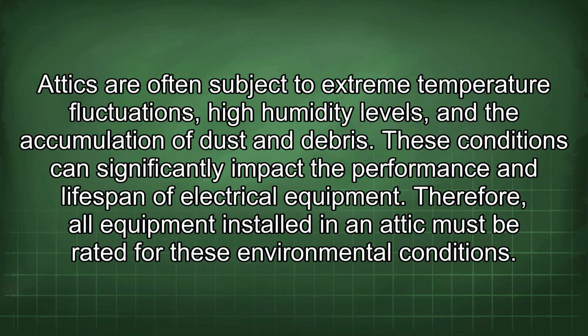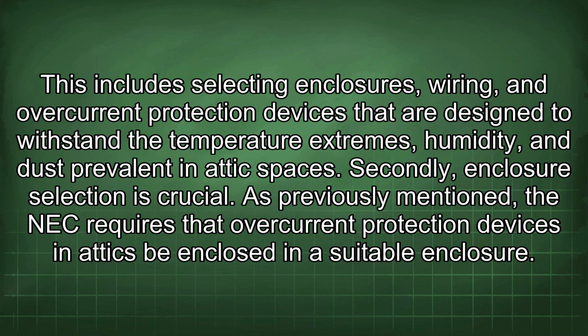Firstly, environmental factors are paramount. Attics are often subject to extreme temperature fluctuations, high humidity levels, and the accumulation of dust and debris. These conditions can significantly impact the performance and lifespan of electrical equipment. Therefore, all equipment installed in an attic must be rated for these environmental conditions. This includes selecting enclosures, wiring, and overcurrent protection devices that are designed to withstand the temperature extremes, humidity, and dust prevalent in attic spaces. Secondly, enclosure selection is crucial.